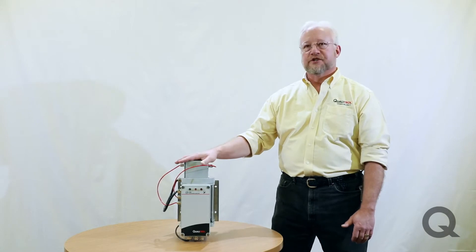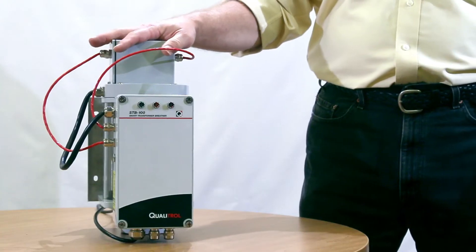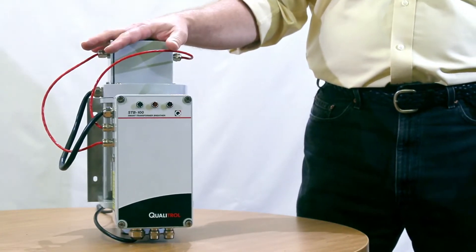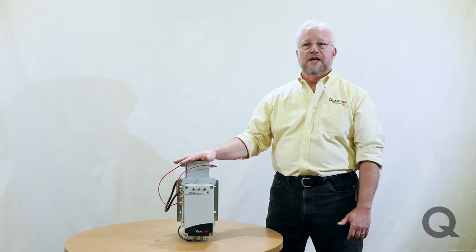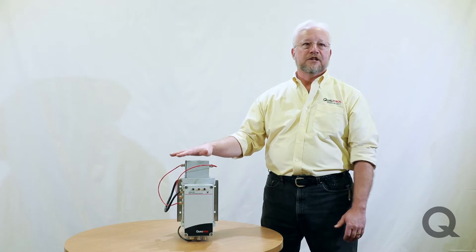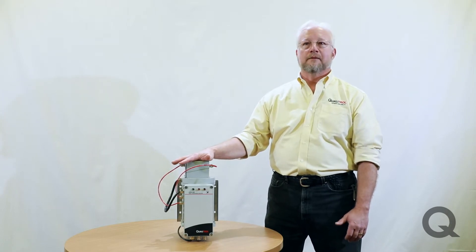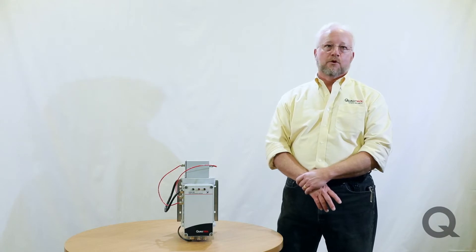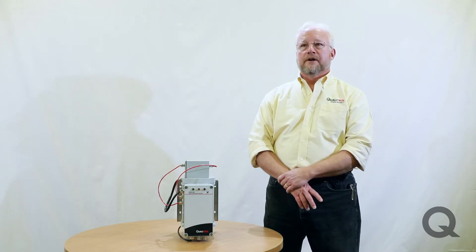There are basically three sizes of the smart breather. This is the baby one, the STB-100. This can be used on either a load tap changer tank or a small conservator tank. The STB-100-2 is a two kilogram unit that you'd use on a larger tank. And then finally we've got the jumbo that you might use on a step-up transformer conservator tank. That is four kilograms of desiccant, weighs 42 pounds. Very useful.